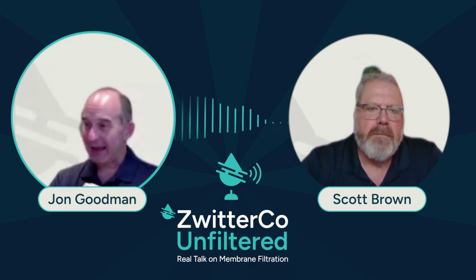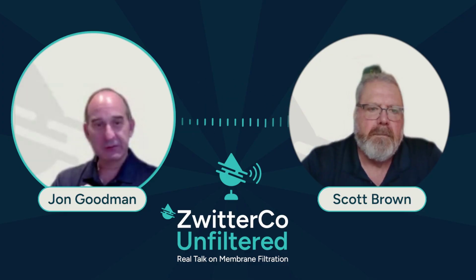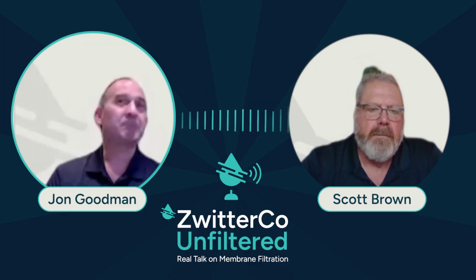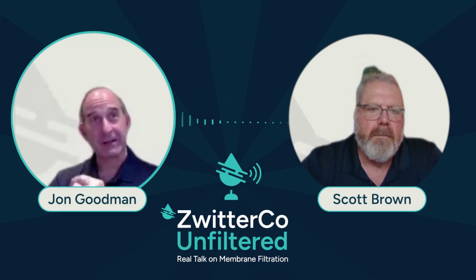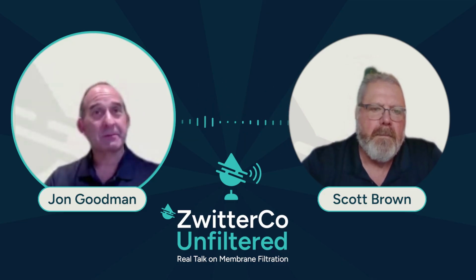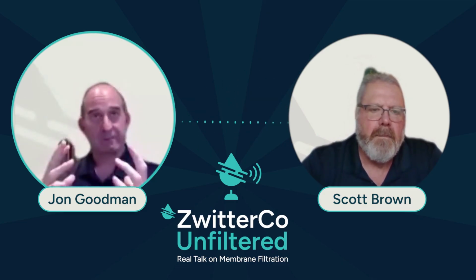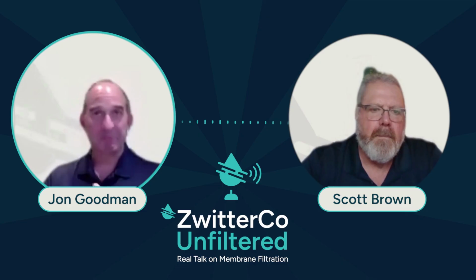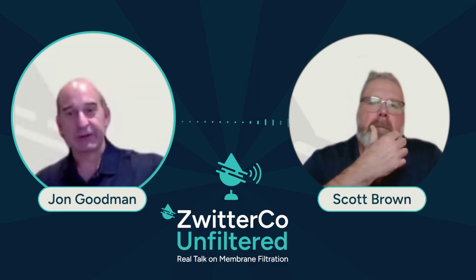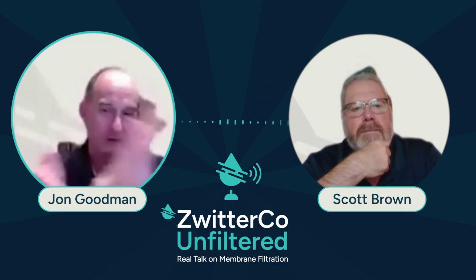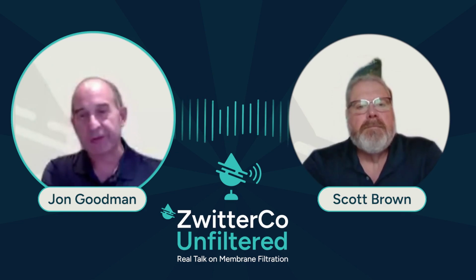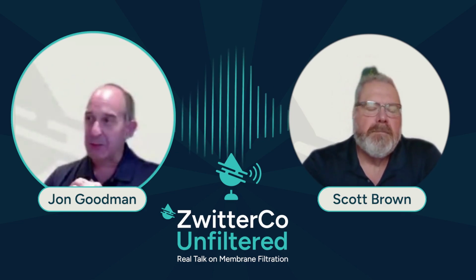What have you got? And basically emptied out the warehouse of all the piperazine, the deashing open NF type membranes and shipped them down to the plant. And they ended up having this blend. And we talked about how do we want to mix them? Do we want to just have tight NF at the front of the system? Do we have the other way around where we have the loose NF at the front and the tight at the back? We talked about how to do it.